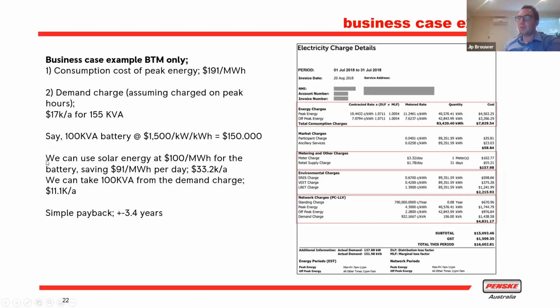Say we have solar on the roof and we add additional solar - I'm quite confident you can get power from that solar panel for $100 per megawatt hour. So if we subtract this figure from this figure, this would be the saving you could achieve compared to the peak energy cost. And if you multiply that by the daily figure, by 365, we come to $33.2 thousand per annum that you could save on your energy bill.